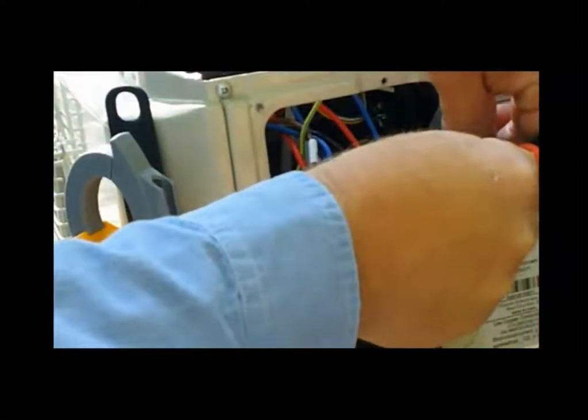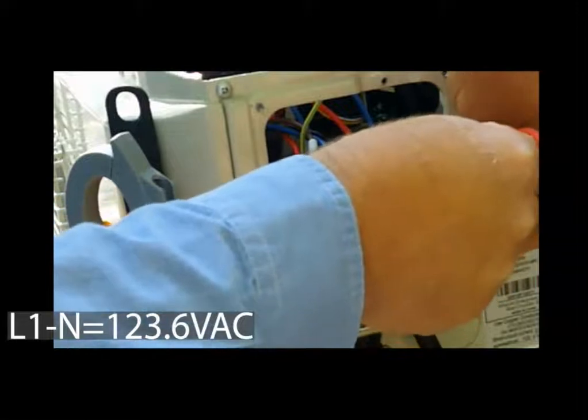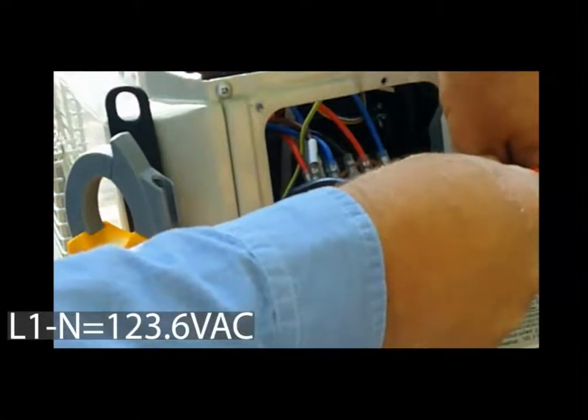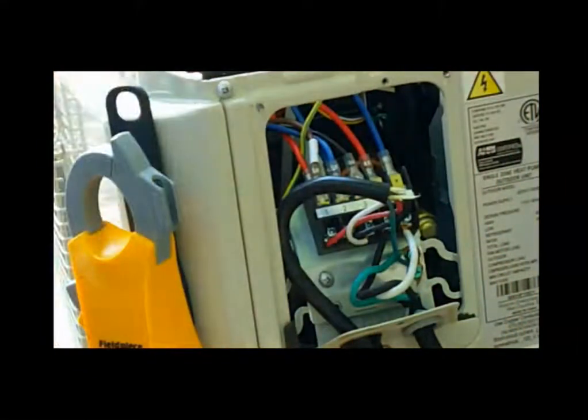So we're going to go ahead and just check neutral to L1, and we've got 123 volts. We can also do the same thing down to ground. We've got 123 volts also. So now what does that do? That gives us our basis for our measurement, because now we're going to be checking our capacitors. When we check our capacitors, we're going to note this. We've got to be between 120 and 140% of our AC power as our DC power on our capacitors. This is checking the IPM on this.